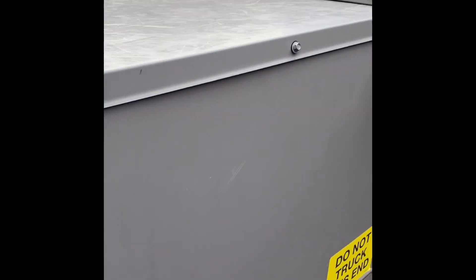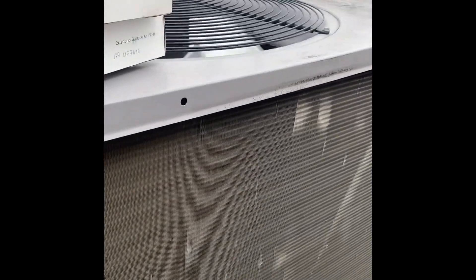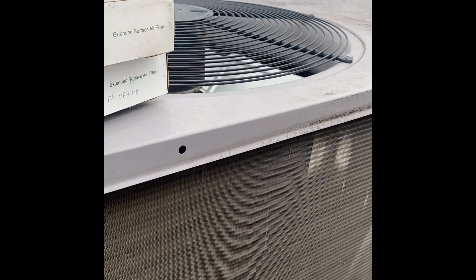So I let it run again, and I'm just trying to verify that it is indeed short cycling. I'll walk around it — door's off, it's getting plenty of air. I did verify with my gauges. But here she goes — definitely short cycling.